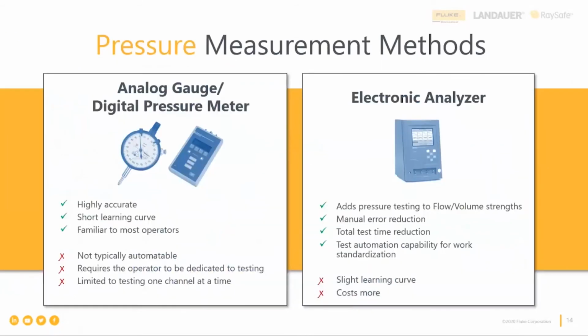All right, so now let's move on to pressure measurement methods. So first of all, why do we need to perform pressure measurement when testing infusion pumps? I don't think I have covered this in the webinar just yet, but there are dynamic monitoring systems within infusion pumps that have the ability to monitor downstream pressure and rapidly detect any sort of occlusion or blockage. And as we mentioned before, the blockages in fluid delivery lead to infusion interruption, and it can be severely harmful to the patient if, for example, some very high-risk medication is being administered to that patient in the moment.